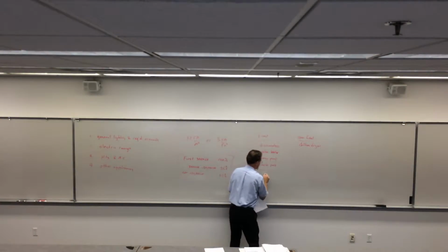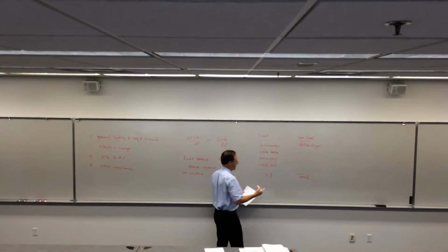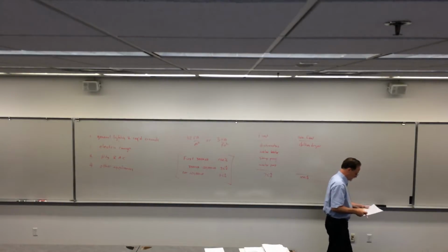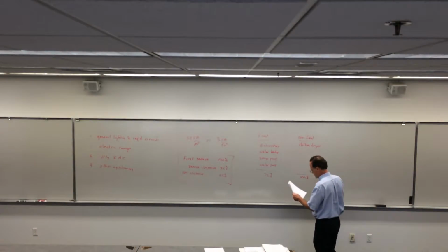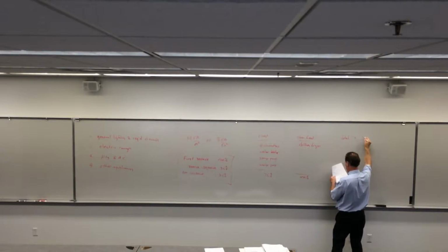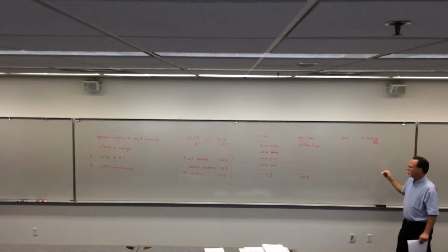So they count 75% of these and 100% of these. And so you can add all these, and there's a list in that example where you add that up and you can get that. And so then you just go through everything we've done and add up all the categories. And in this example, you ended up with the total equal to 27,574 volt amps. And that's why you keep it all the way through in volt amps and don't convert it till the very end, because then you come in with the service.